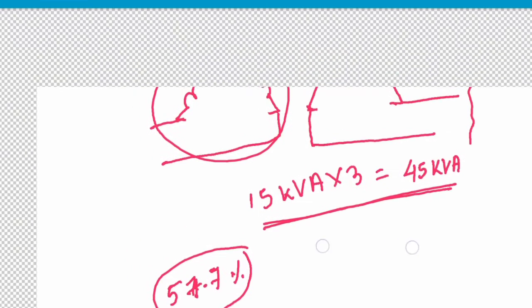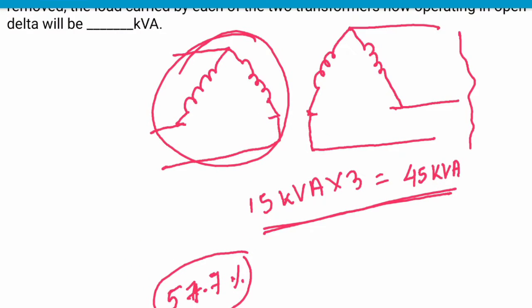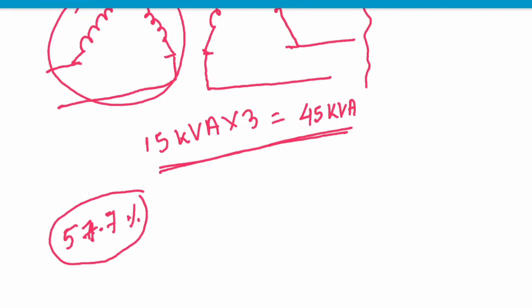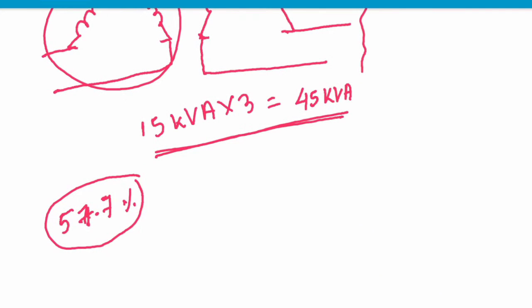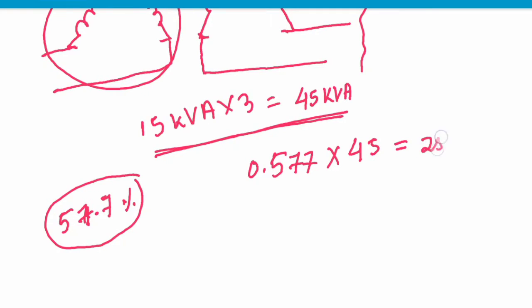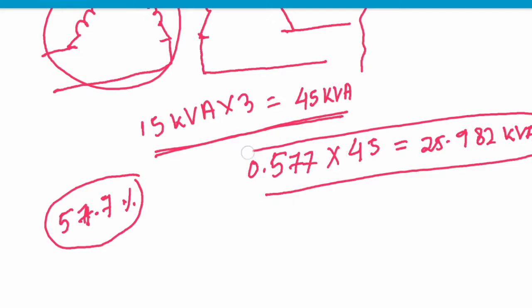Because we were using three transformers to provide three-phase supply, and now we are using only two transformers, the efficiency will decrease to 57.7%. Now what will be the new kVA rating? The new kVA rating will be 0.577 into 45, which is around 25.982 kVA. This is the new rating of the transformer bank. This 57.7% is also known as 1 by root 3 of the previous one.